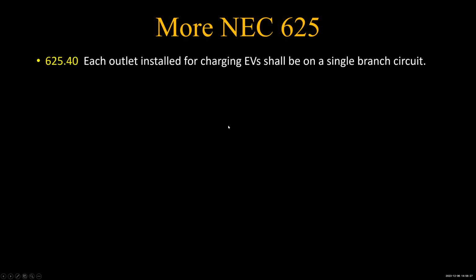A little more of 625, each outlet has to be on a single branch circuit. Yes and no, there's settings that say, yes, each outlet's on a single branch circuit. On the other hand, there are provisions for sharing, but that's done by software. But the design, you design as though it's on its own branch circuit.